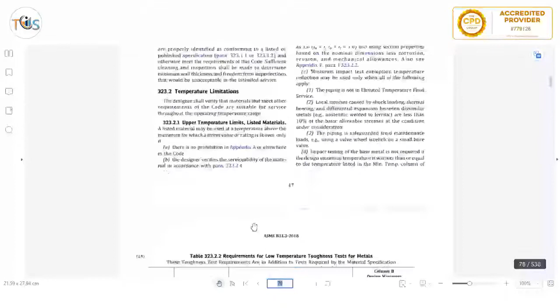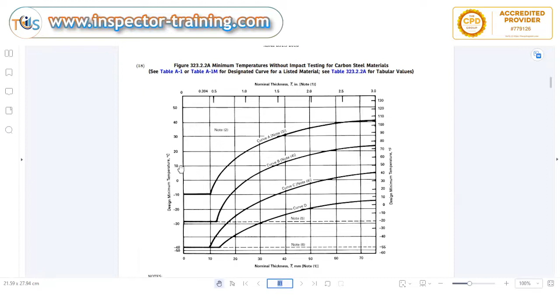Say for millimeter, I'm just looking at it. And then the degree centigrade, the temperature, is actually the working, the minimum design metal temperature. So you draw an imaginary line here and come here. If you say 40 millimeter and the working temperature is 10 degree, impact test is required because it's below the curve, and it's say on curve A. Now, for curve A, definitely required. For curve B, curve C, curve D, it depends which curve that material belongs to. That depends on the toughness of the material.